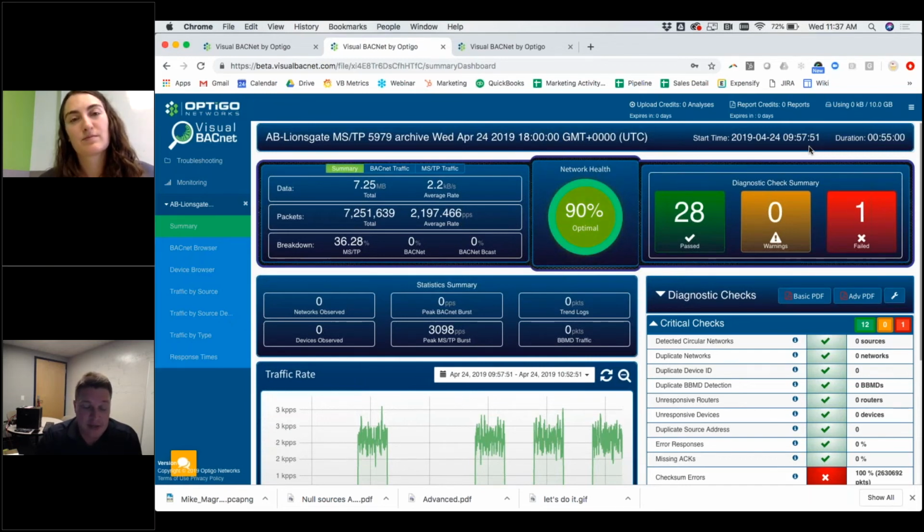In the Navy Yard case, I was actually pitching it to the professors that said, "Oh, we need to sample it at this rate," and I basically told them, at this sampling rate, the data you're getting is worthless because the system can't function at that rate. Once they backed it off, we were able to see an improvement in the building, and they've done a lot of rewiring and a bunch of different things, and the building now functions.